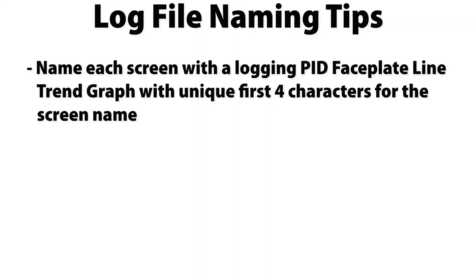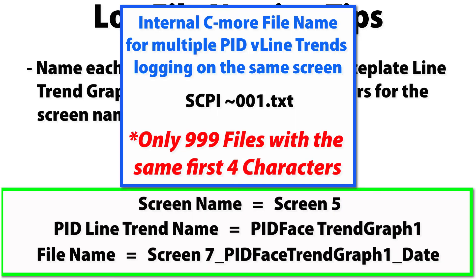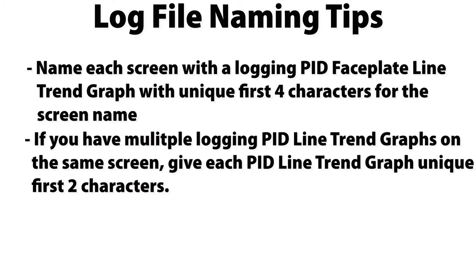So, if you need to log multiple PID faceplate graphs, make sure to name each screen that has a logging PID trend graph with unique first 4 characters of the screen name. Now, if you have multiple PID trend graphs logging on the same screen, the internal file will be the first 2 letters of the screen and the next 2 letters will come from the PID faceplate name. With this, just make sure that the PID faceplate graph names have unique first 2 characters.